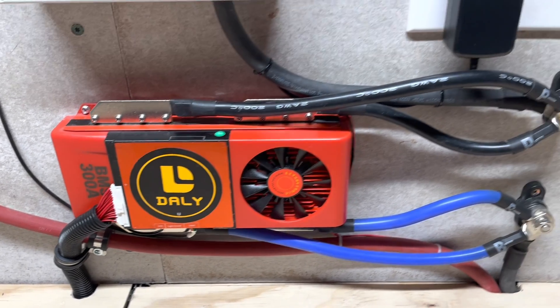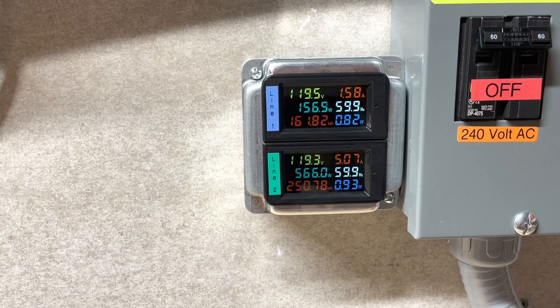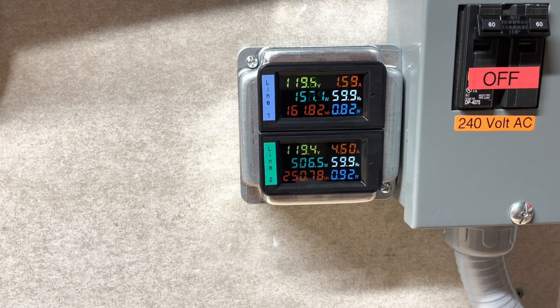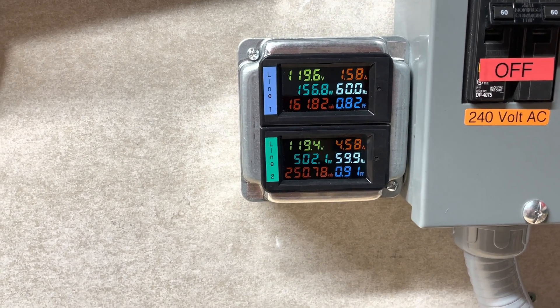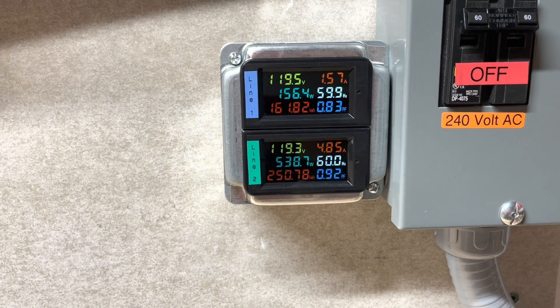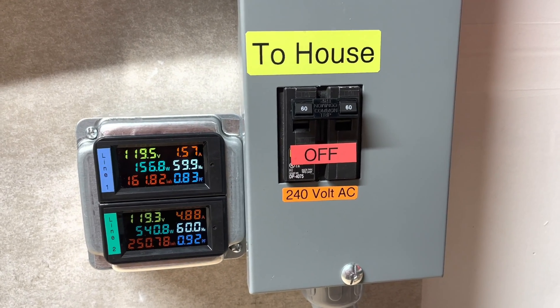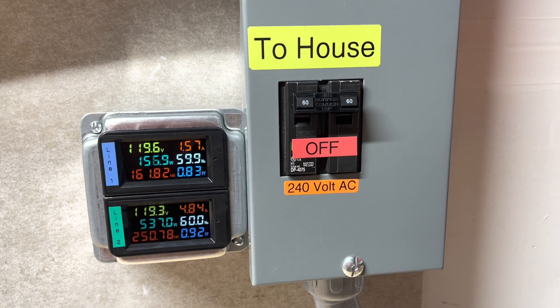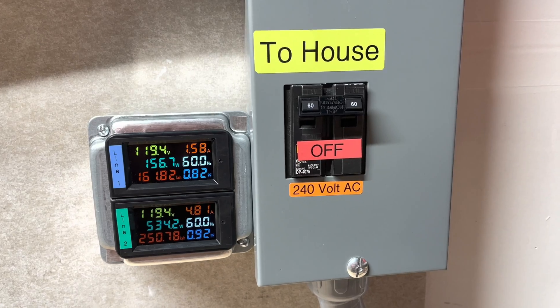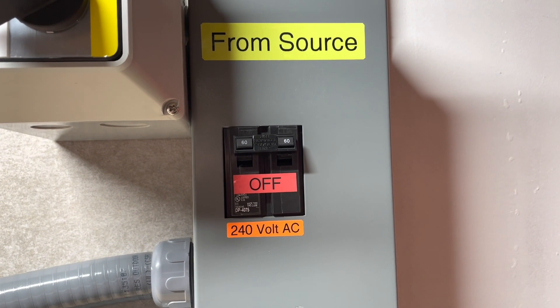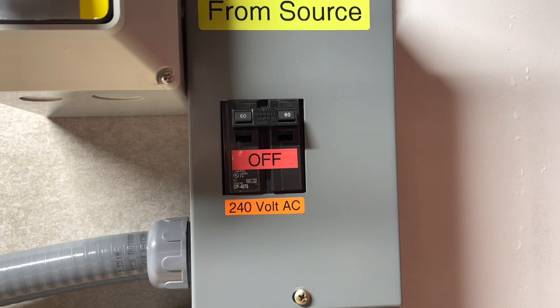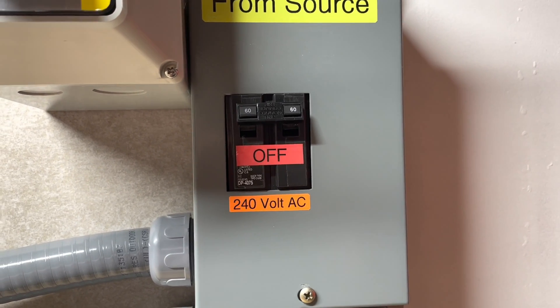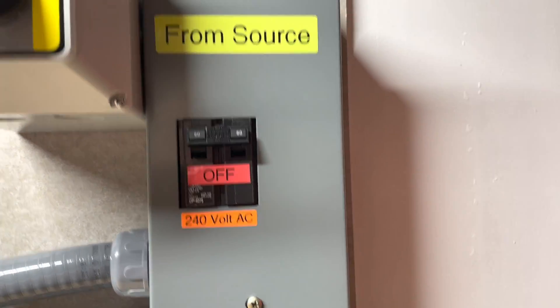Got these little meters so I can check each side of my lines, how well it's balanced. So if I've been pulling too much off of one side, I can go to the breaker box out there and swap some breakers around or swap the lines on the breakers and balance my system a little bit better. Got the disconnect going to the panels outside, and there's a breaker on the panel where it feeds in. It's a 70 amp, this is a 60. If I want something to trip somewhere, I want it to happen here.